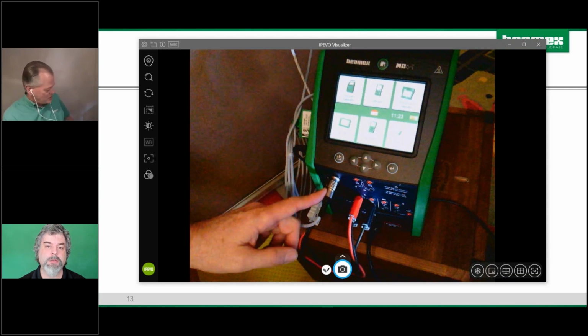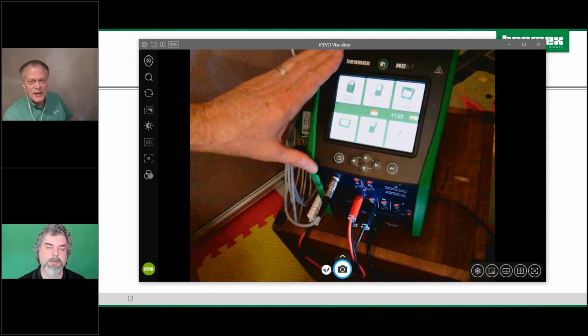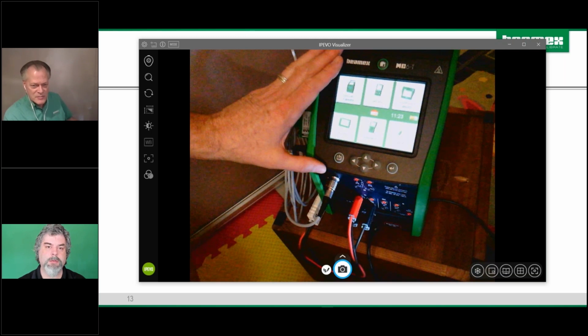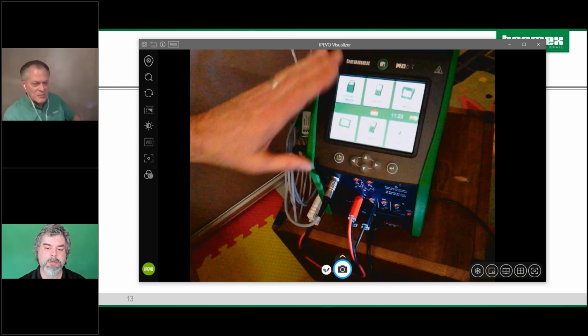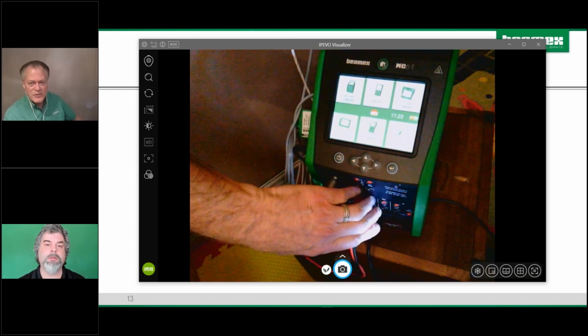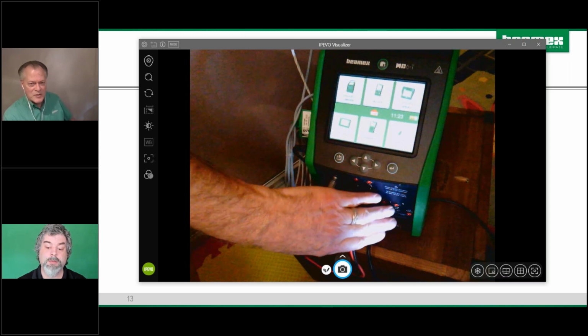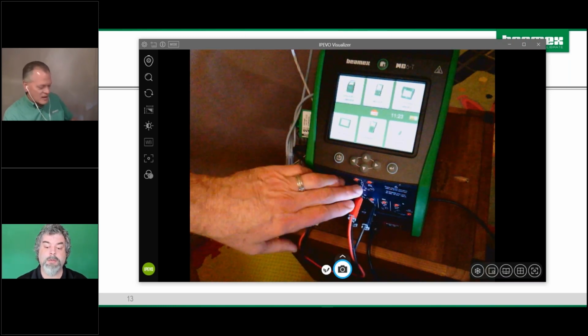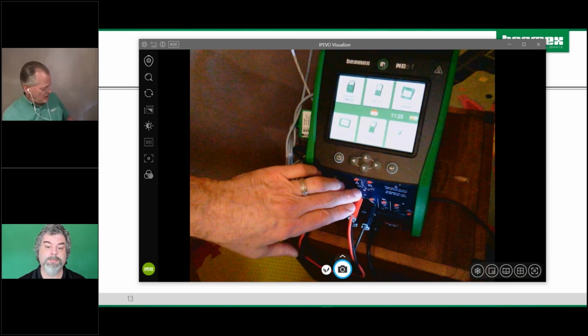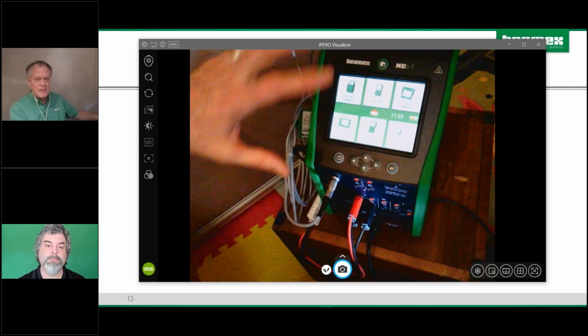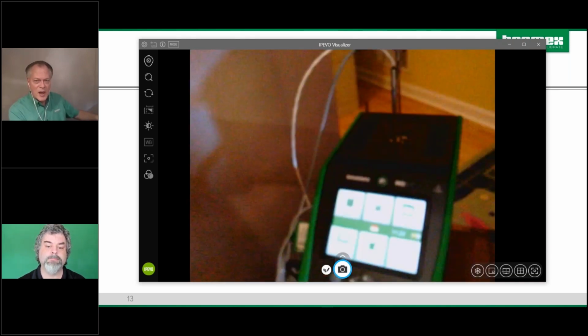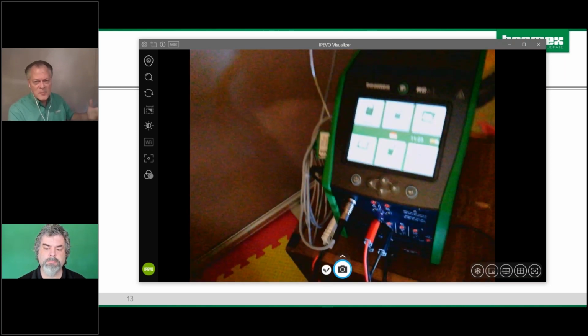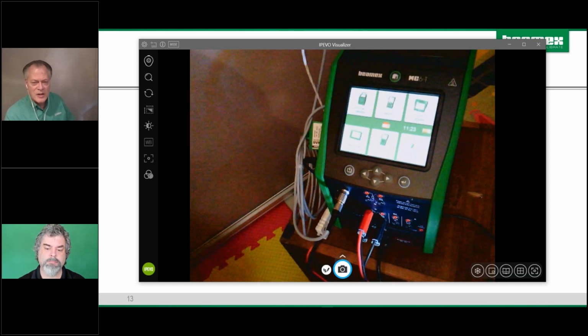Well, this is our new model that combines our field calibrator, which has all these terminals for doing milliamps, frequency, and other parameters, but we've added an extra temperature connection and put the dry block behind it. So it's really a calibrator - we call it a temperature calibrator, but it can also do pressure and electrical control signals. Oh, okay.